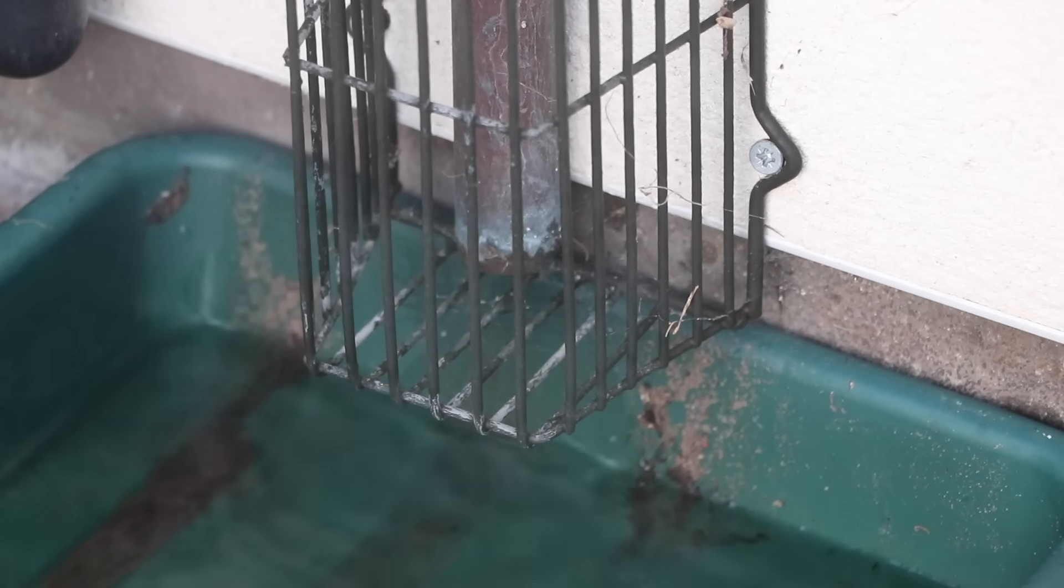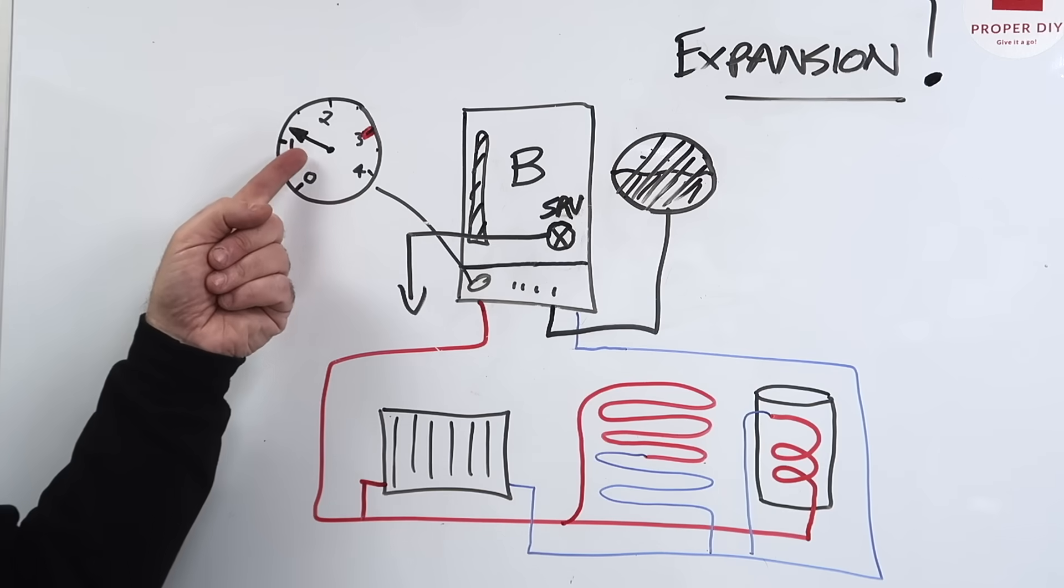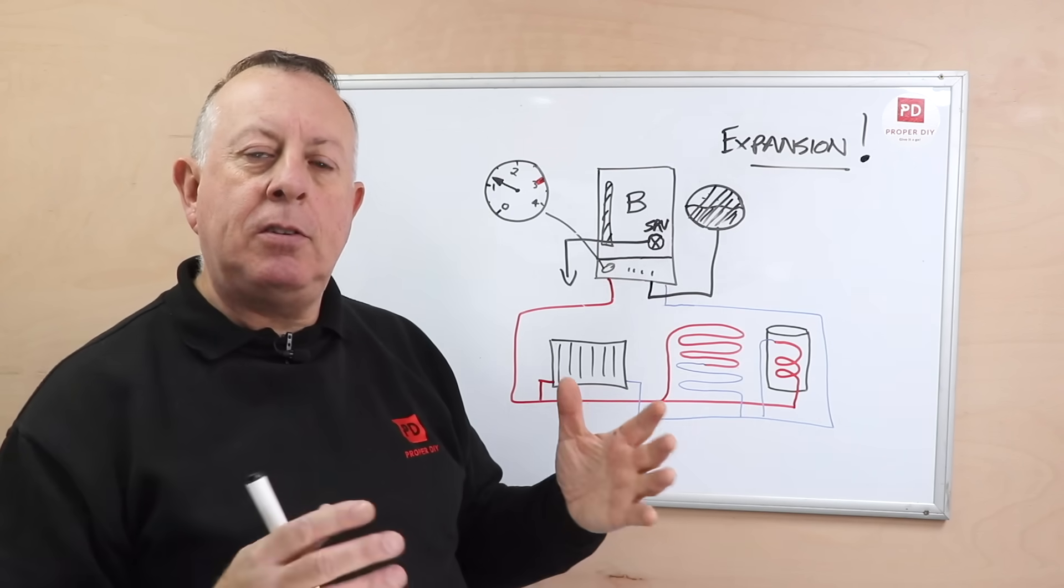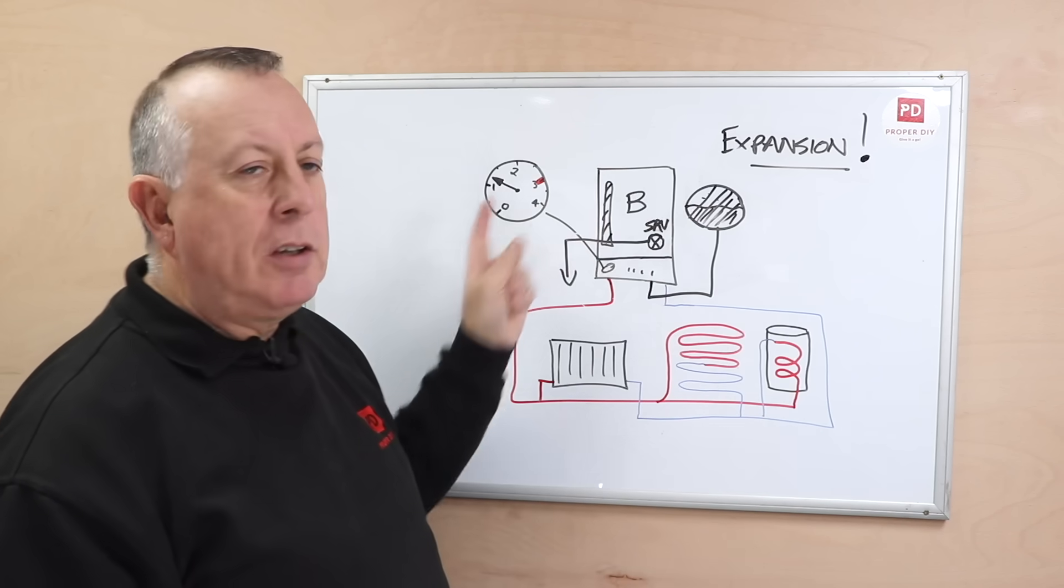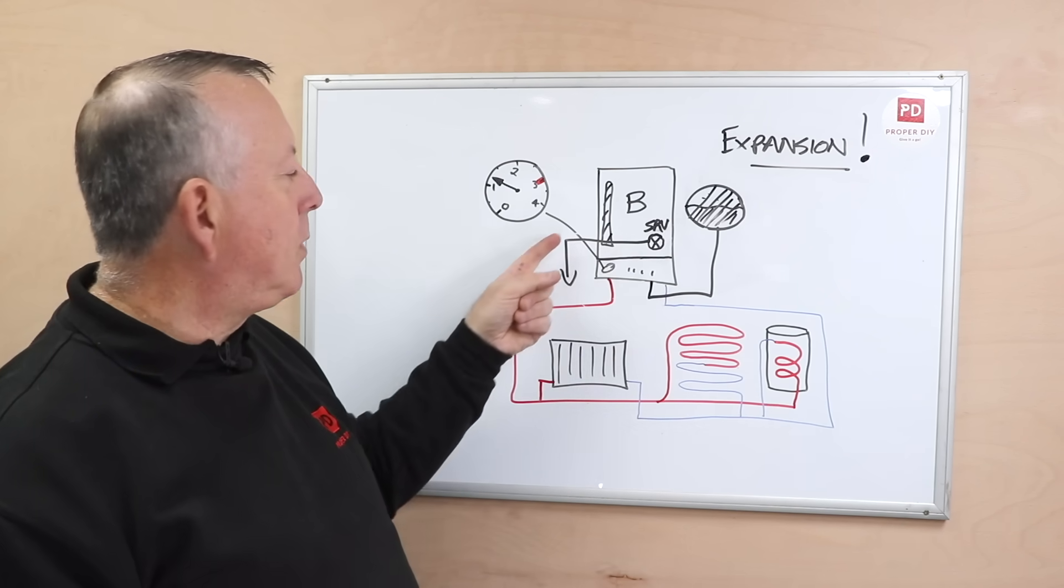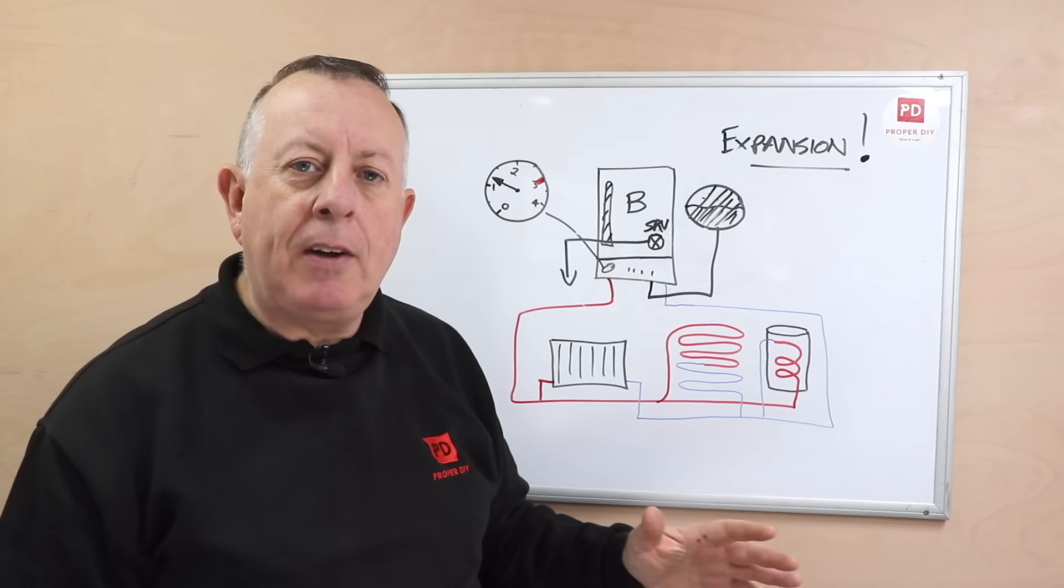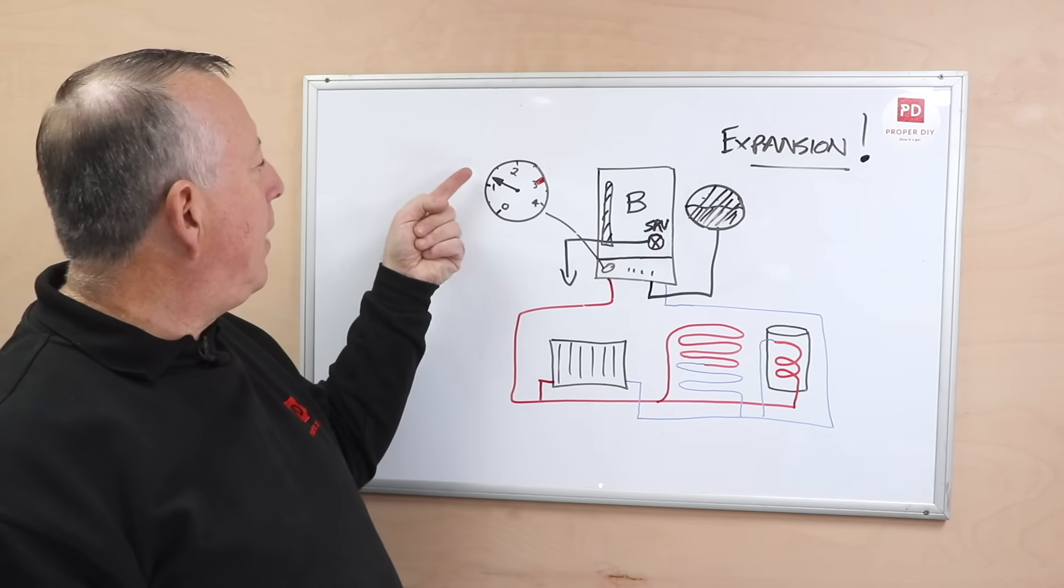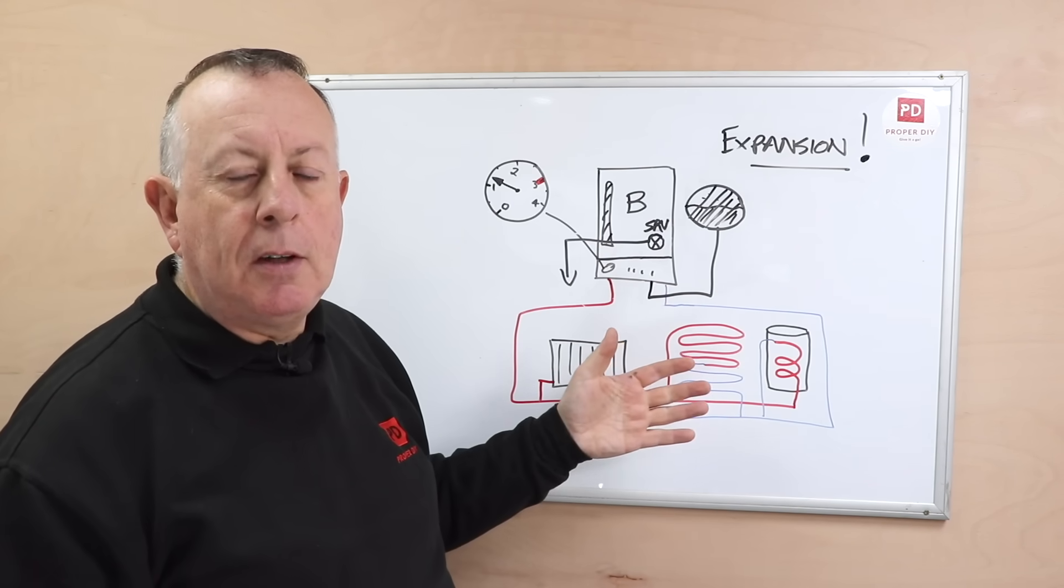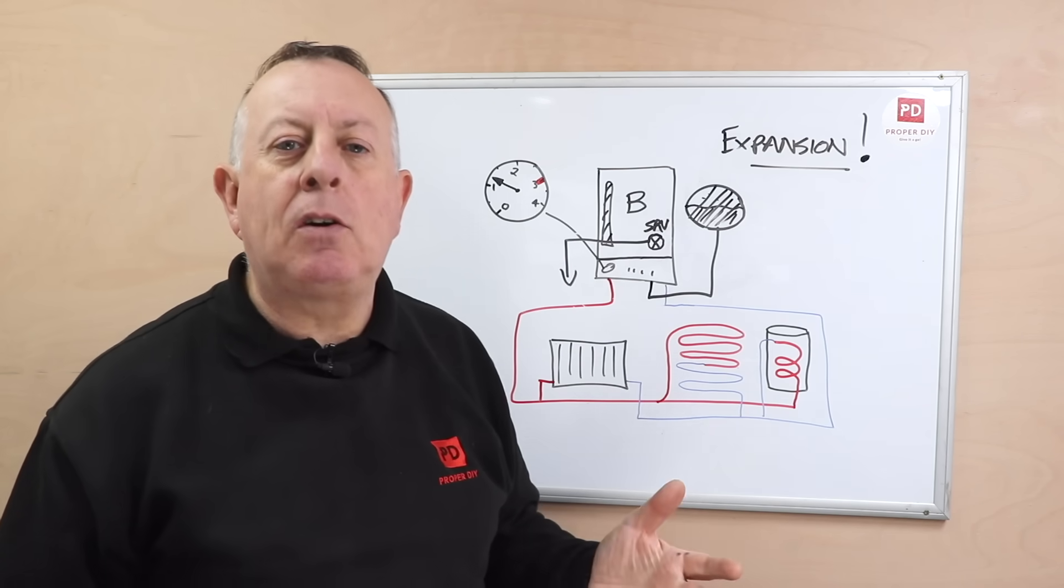So if you have a failed expansion tank, what you'll find is when the system is off it's easy to pressurize it to the right pressure, which is one to one and a half bar. But as soon as you turn it on, the water's got nowhere to expand to, the safety relief valve kicks in and it will dump water out of the vent out the back of your house. Once the system is turned off again and everything's cooled down, you'll find that that pressure is now a lot lower because it's got rid of water in the system, and the tray that you put out the back of your house underneath the vent has now got water in it.